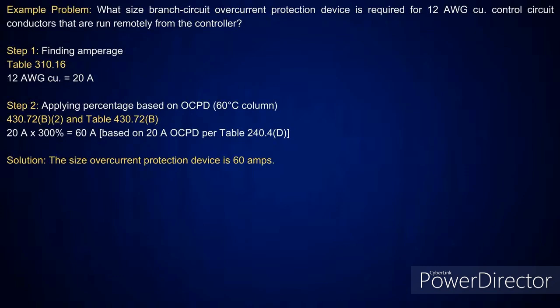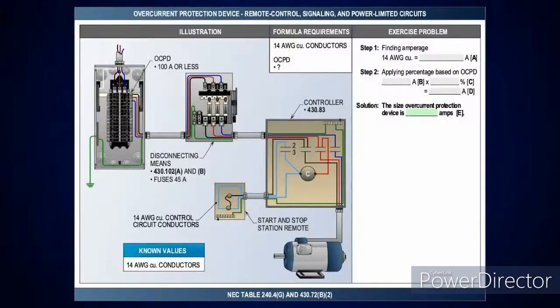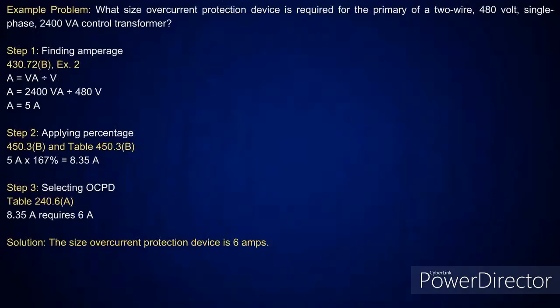All we're doing is showing you below the table and the percentages. How did they make that determination? This is how they did it. And then you'll see here we have the control circuit conductors run remotely over here. And then you need to use table 310.16, 75 degrees C column, take it at 300%, and then size your overcurrent protection device accordingly.